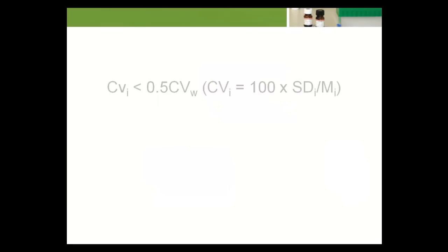If there is no bias between analytical modules, all modules have the same mean, and each module just meets the goal of CVI less than 0.5 CVW, CVI equals 100 times SDI over MI, then the total analytical system will also just meet the goal.